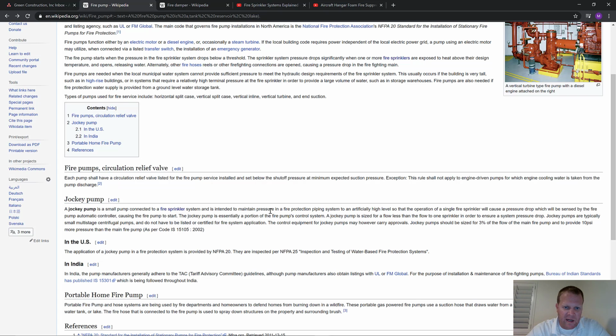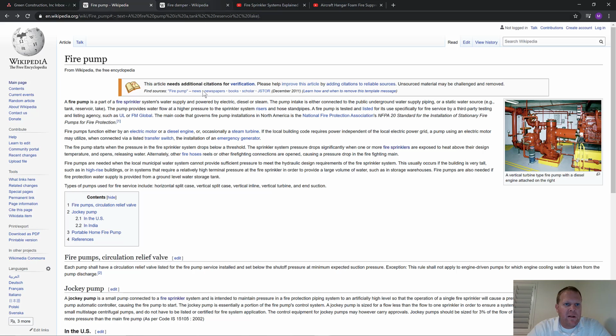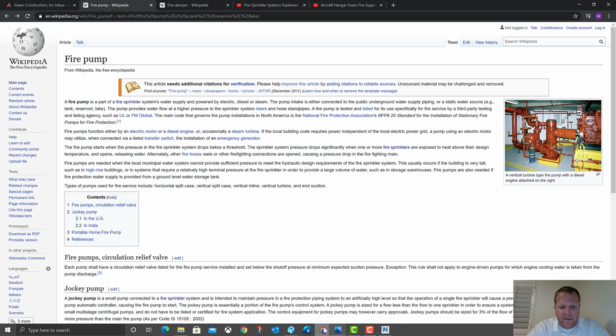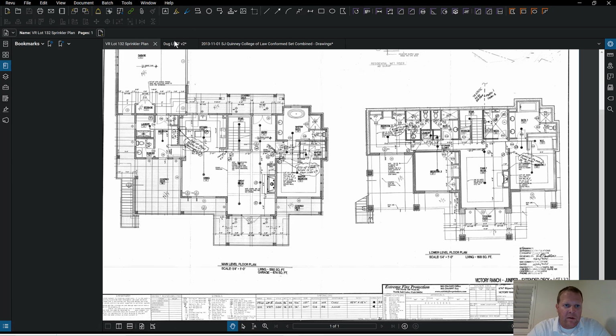It's just aiding the suppression system to stay under pressure so that the fire pump doesn't turn on based off of a pressure drop, which would be a false turning on. And these big pumps are pretty big, and I don't think you want them to just cycle on and off. That's why they have the jockey pump, to put a little bit more water in and pressurize the system again. So jockey pump is another term. Let's look at a set of drawings here.